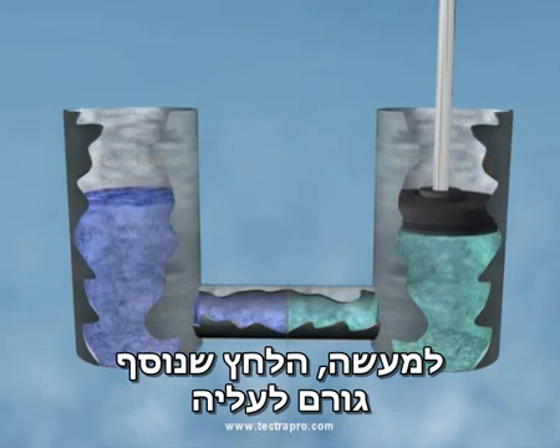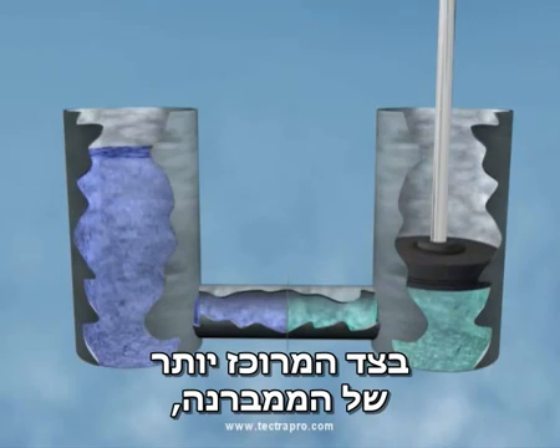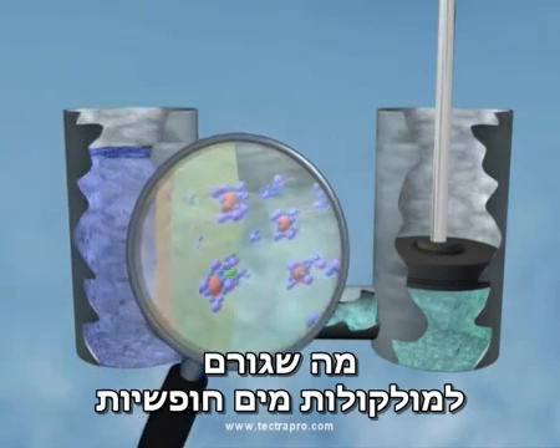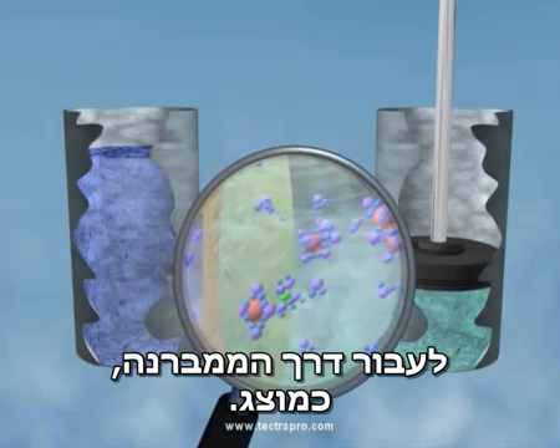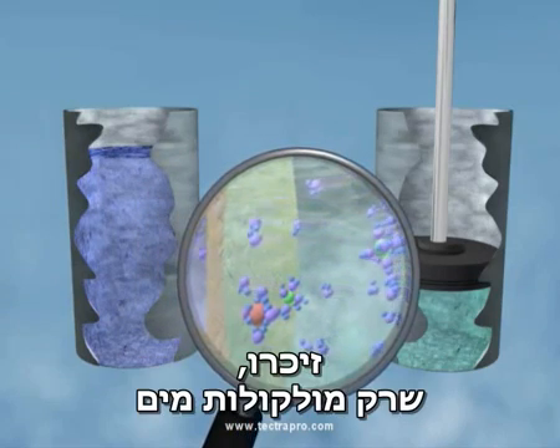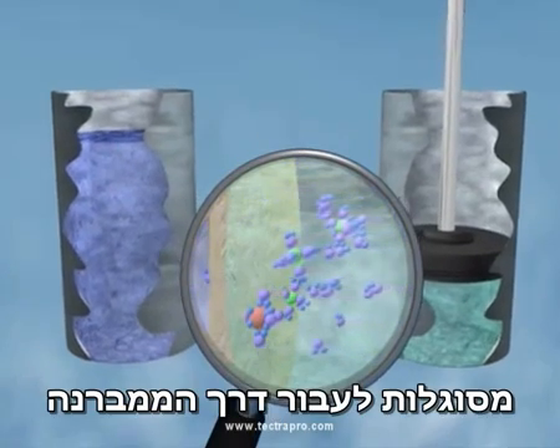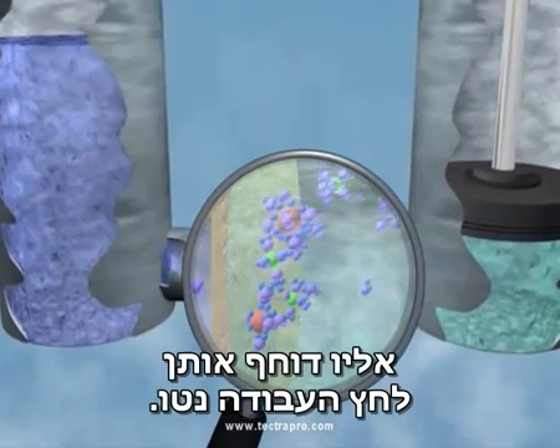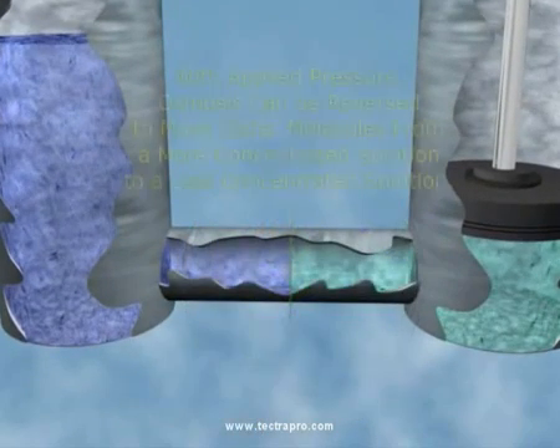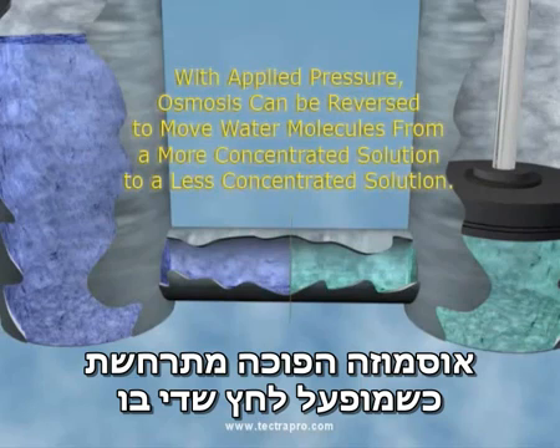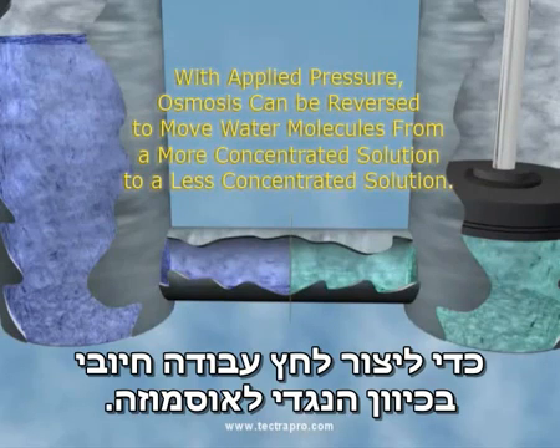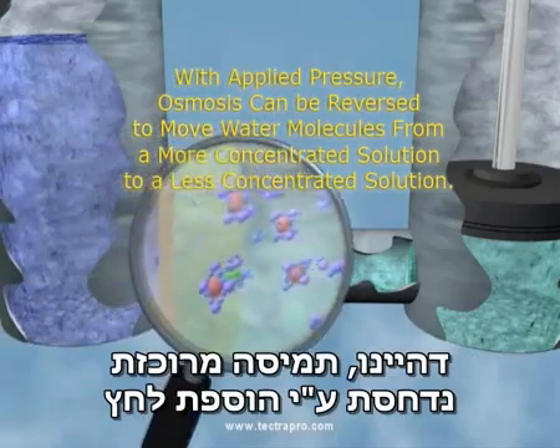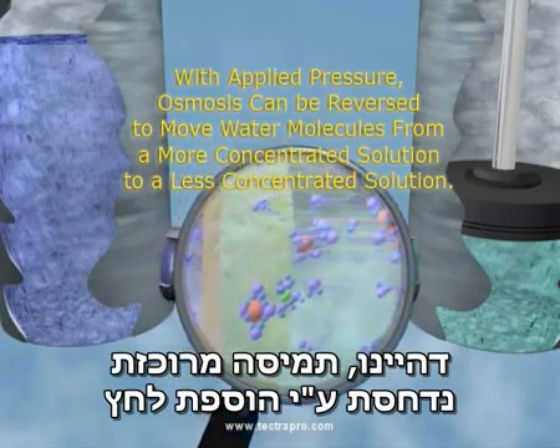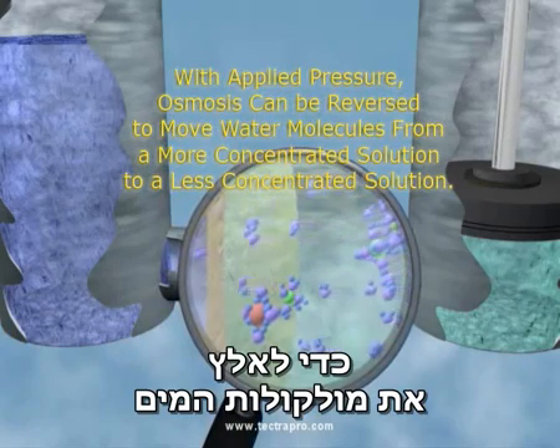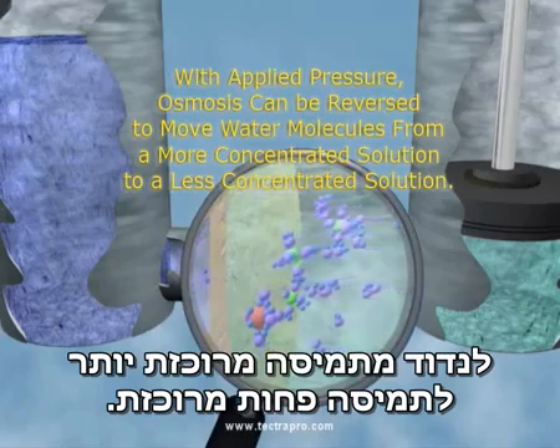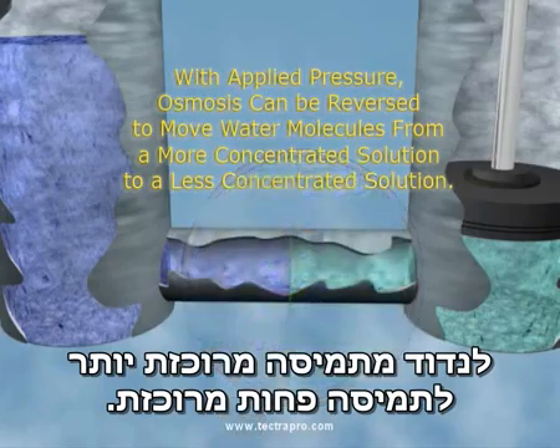Basically, the added pressure causes more collisions between water molecules on the more concentrated side of the membrane, which forces free water molecules to be pushed across the membrane as shown. Remember that only water molecules can pass through the membrane, and they will pass in the direction that the net driving pressure pushes them. Reverse osmosis occurs when enough pressure is applied to cause a positive net driving pressure in the direction opposing osmosis. That is, a concentrated solution is squeezed by the application of additional pressure to force water molecules to migrate from a more concentrated solution to a less concentrated solution.